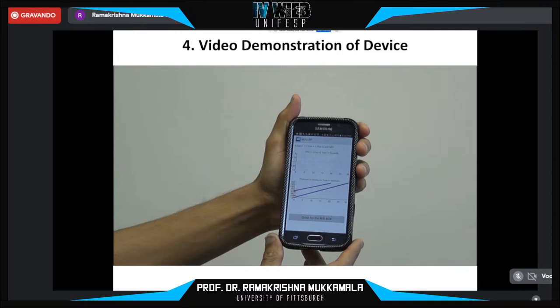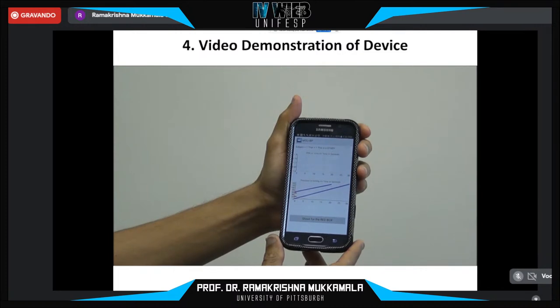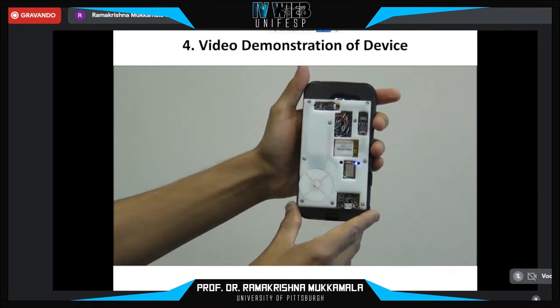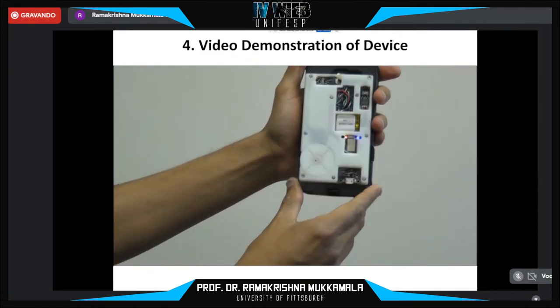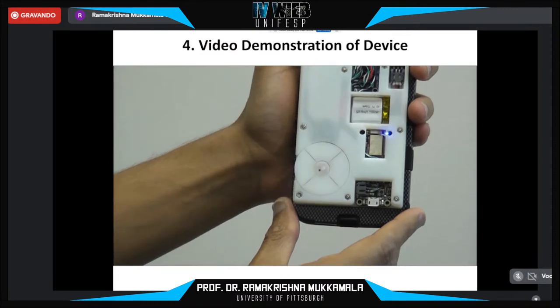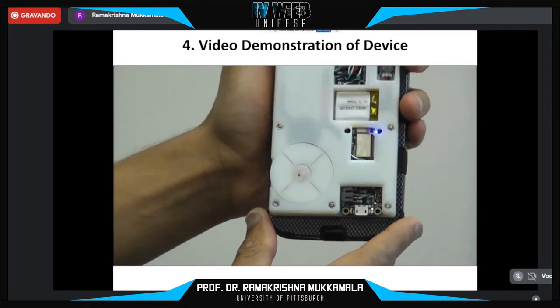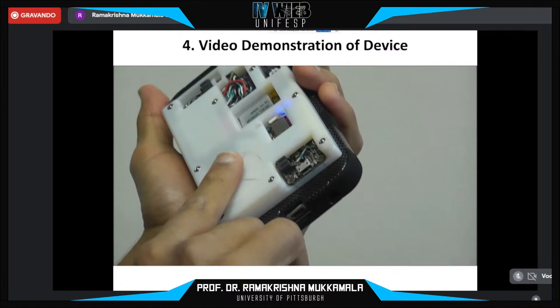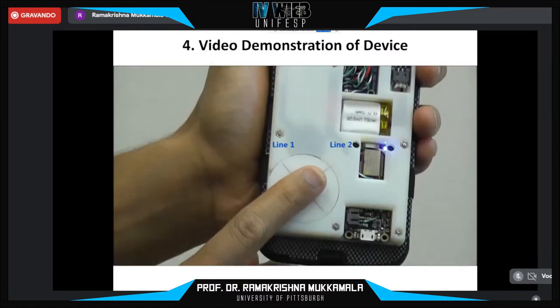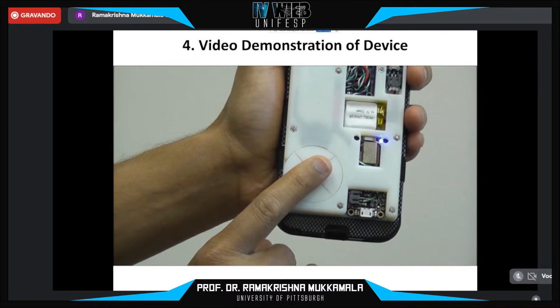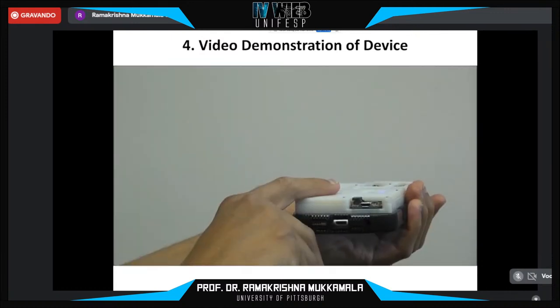A user interacts with the device to measure blood pressure in three steps. First, the user places his index finger on the sensor unit on the back of the phone according to the line indicators. In particular, the base of the fingernail is aligned with line 1, and the long axis of the finger is centered on line 2. The user places the finger flat on the encasing rather than at an angle.